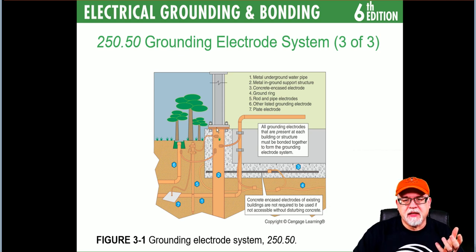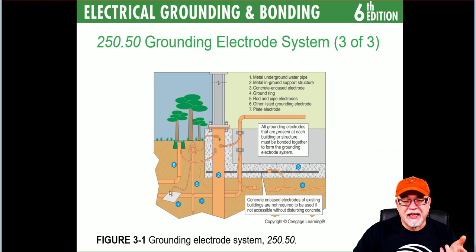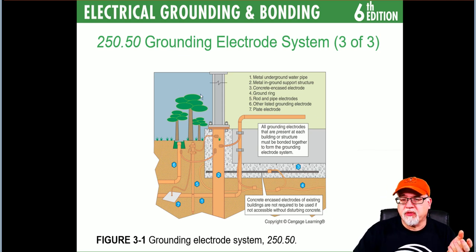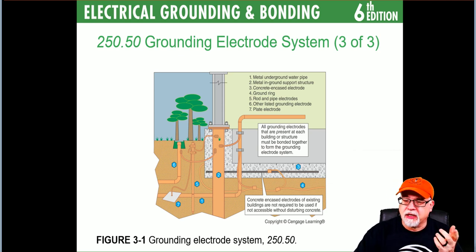An interesting thing many people think is that the grounding electrode conductor to ground rods has to be continuous through it. If you supplement the ground rod with another electrode because it doesn't meet 25 ohms or less — in this example supplemented with a plate — the grounding electrode conductor theoretically stops at the first rod, and the connection to the next electrode becomes a bonding jumper. All these types of things get covered in our course.